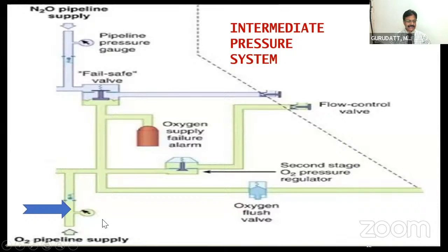These pipelines enter the intermediate system because there are separate connections and separate inlets on the back of the workstations for the connection of these pipelines. They have a pressure of roughly 55 to 60 psig, and the connections are also diameter indexed. So the diameter index safety system, or non-interchangeable screw threading, is there. These things were discussed in detail in my last lecture, so I'm not going to discuss much about this pipeline supply that is part of the intermediate pressure system.